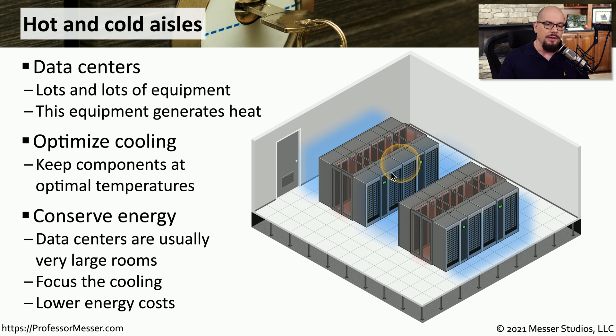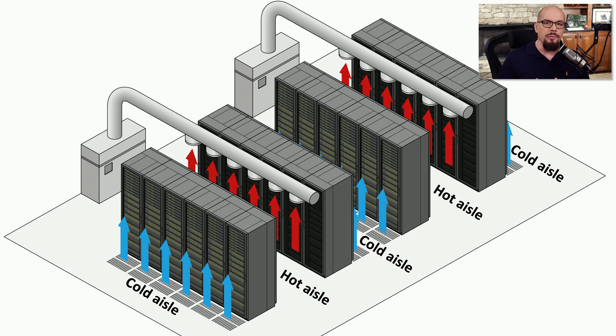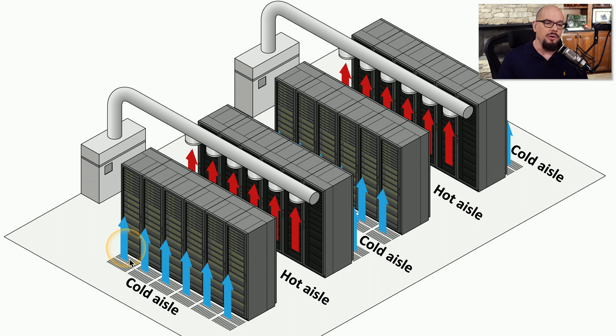One of the environmental challenges data center administrators face is keeping equipment cool in a very large room where equipment occupies a relatively small amount of space. It would be much better to only cool the sections where cooling is required. To do that, we separate the room into cold aisles and hot aisles. Cool air is provided to the equipment on the cold aisle, sent through the equipment and heated up into the hot aisle, where ventilation equipment captures the hot air and sends it back into the cooling system to be recycled into the cold aisle.